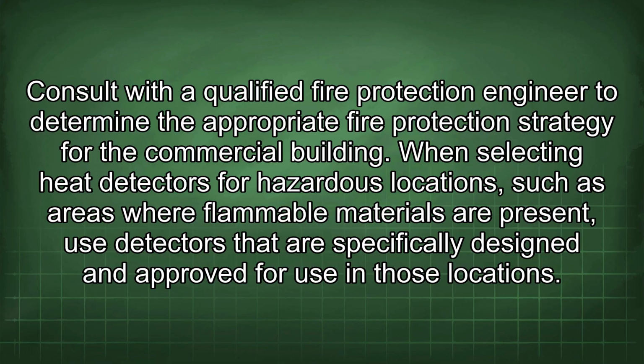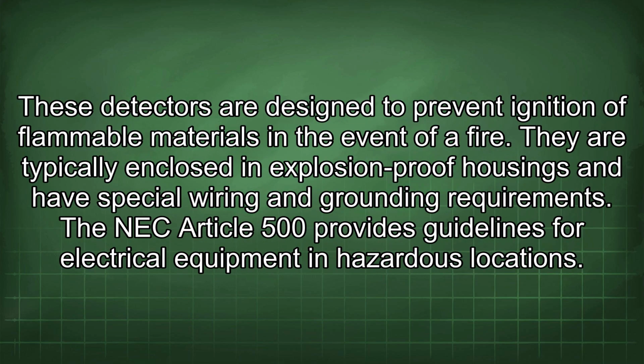When selecting heat detectors for hazardous locations, such as areas where flammable materials are present, use detectors that are specifically designed and approved for use in those locations. These detectors are designed to prevent ignition of flammable materials in the event of a fire. They are typically enclosed in explosion-proof housings and have special wiring and grounding requirements. The NEC Article 500 provides guidelines for electrical equipment in hazardous locations.